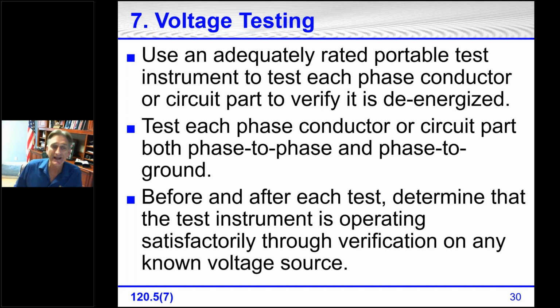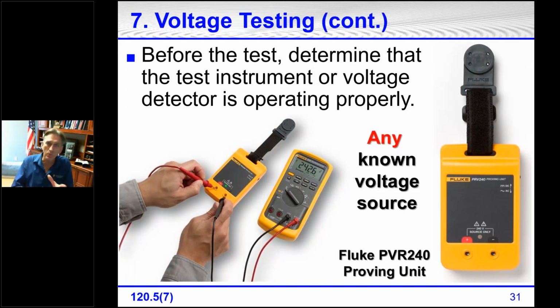Before the test and after the test, make sure that the test instrument, the voltage detector, is working properly through verification on any known voltage source. In testing for the absence of voltage, we have to test our tester, test for the absence of voltage, and test our tester again. Fluke makes what they call a proving unit. This is great. It has 4 AA batteries, an AC or DC switch, and gives roughly 240 volts.